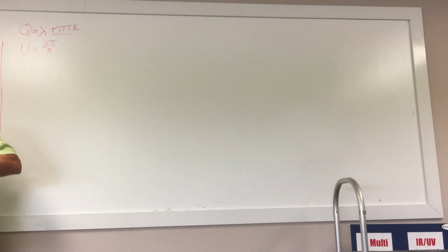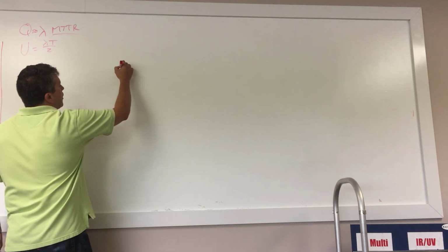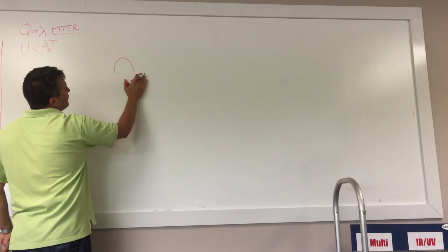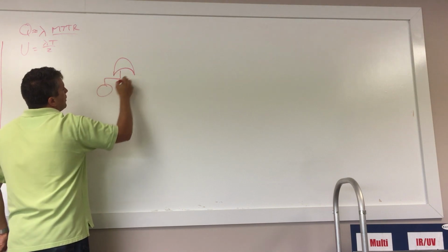Okay, so that was 1 out of 2. Let me talk about 2 out of 2. The most important term that we're always concerned about with 2 out of 2 is going to be the DU term, dangerous undetected. So now we're going to go back into our fault tree, but instead of an AND gate, now we have an OR gate.